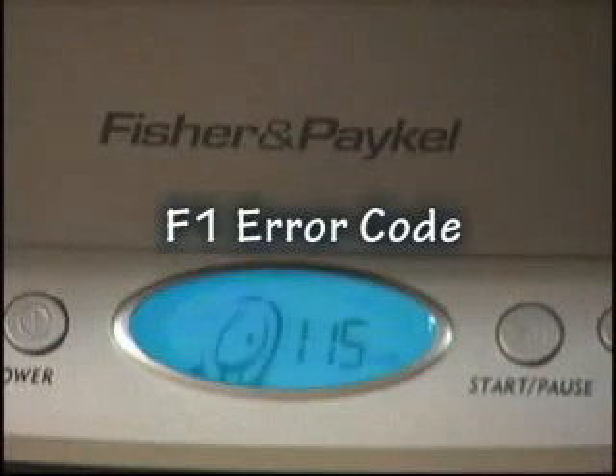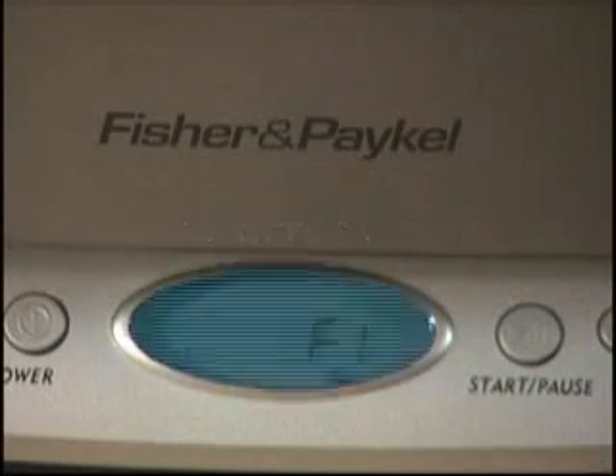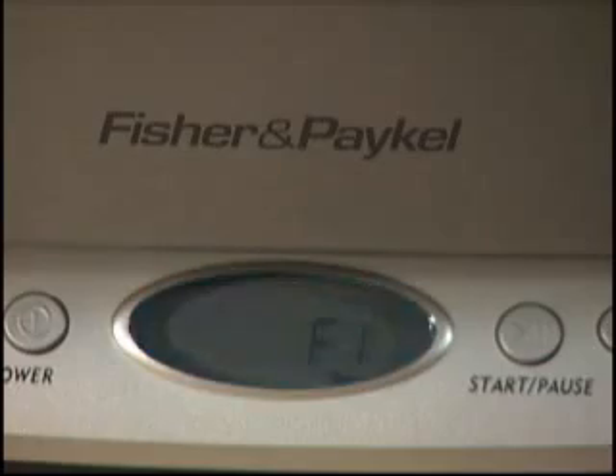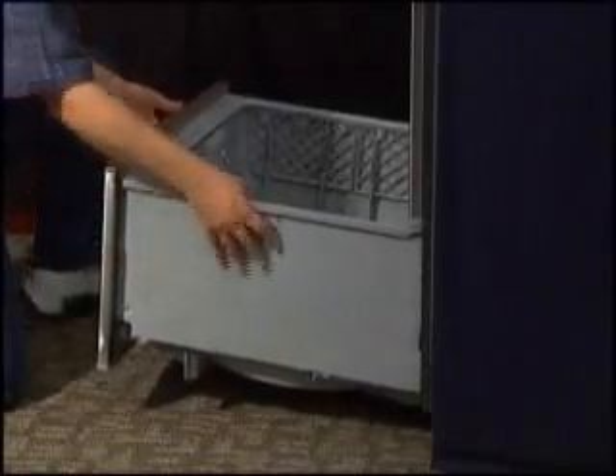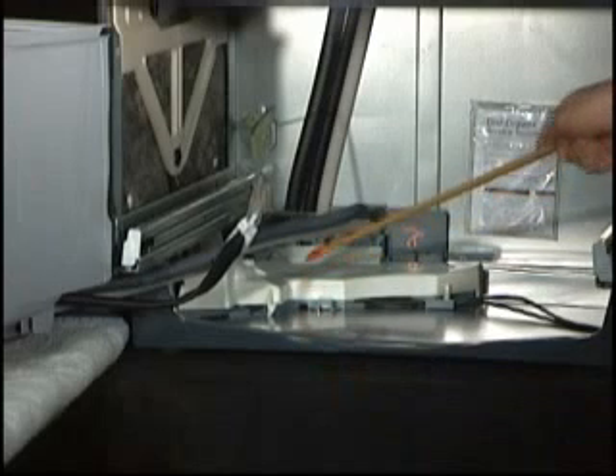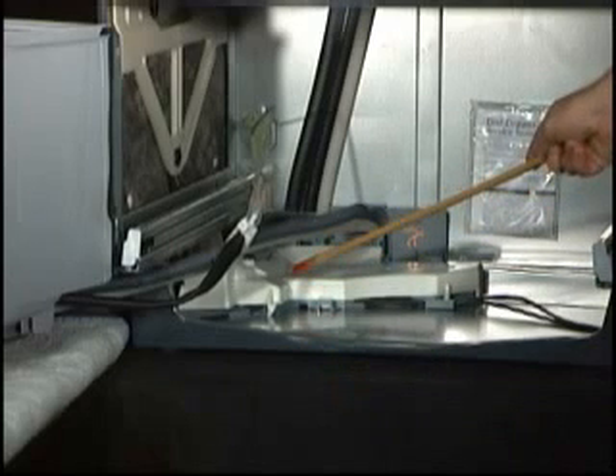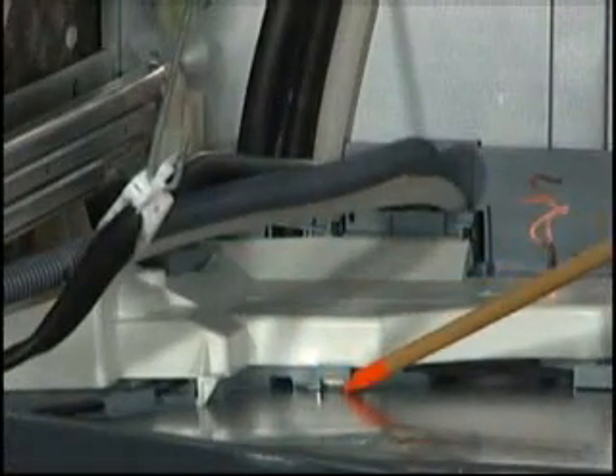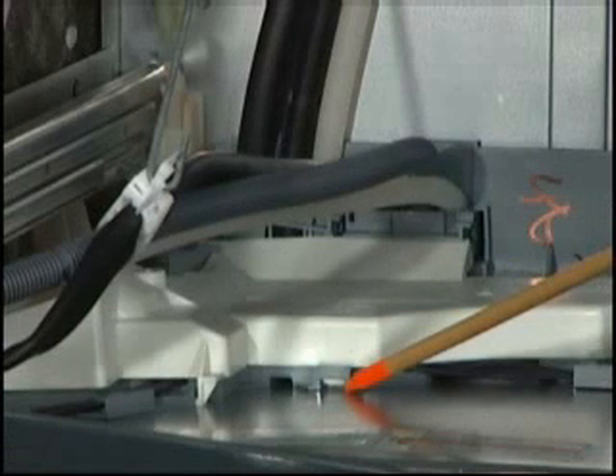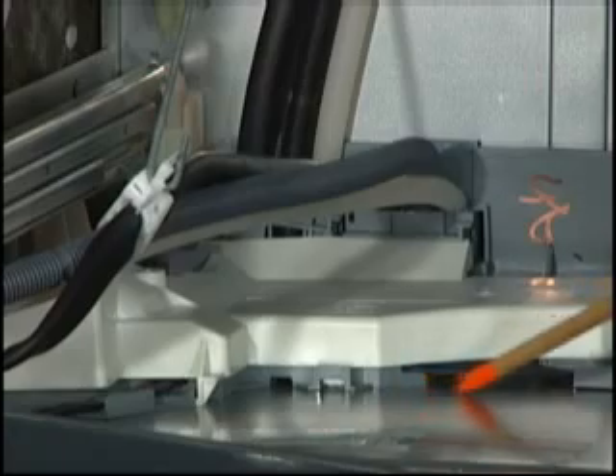An F1 error code signals that a flooded condition has occurred. When both drawers are indicating an F1 error code, remove the lower drawer. The flood switch is located in the bottom back left corner under the plastic cover. To remove the cover, use a flat blade screwdriver to depress a tab on the front center of the cover. With the tab depressed, slide the cover to the right and pull up on the cover to remove.